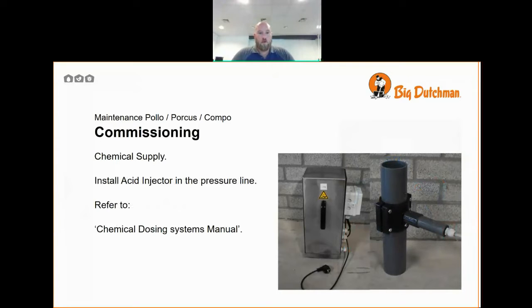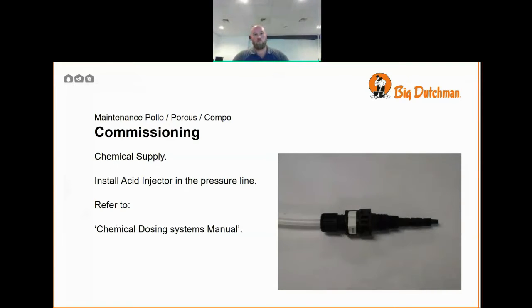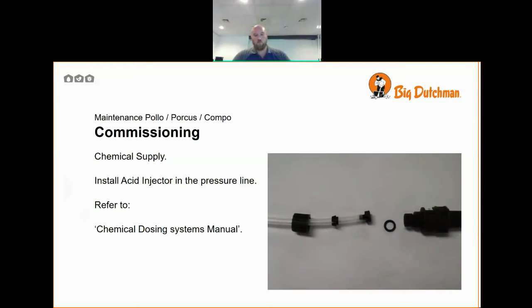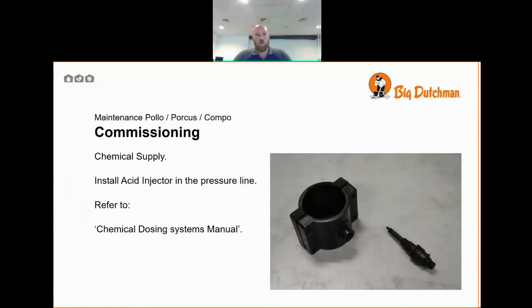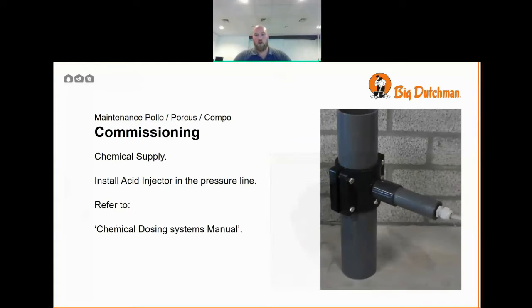Chemical supply. Install the acid injector in the pressure line. Refer to the chemical dosing systems manual for more. This is the assembled injector. It comes in a few parts. We slide the collars over the hose, insert the bung into the end of the hose, and then screw it onto the injector. The injector will screw into a drill saddle, as pictured, and then a protective housing to prevent any whipping or pulling of the hose damaging the injector is fitted over the top.